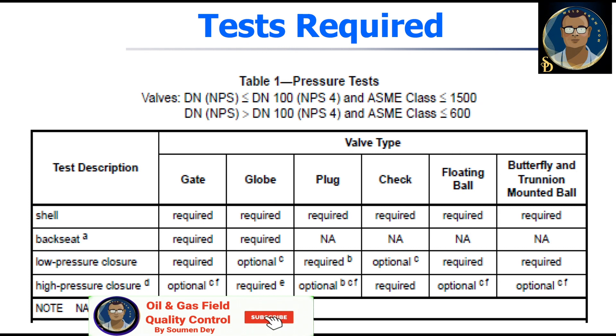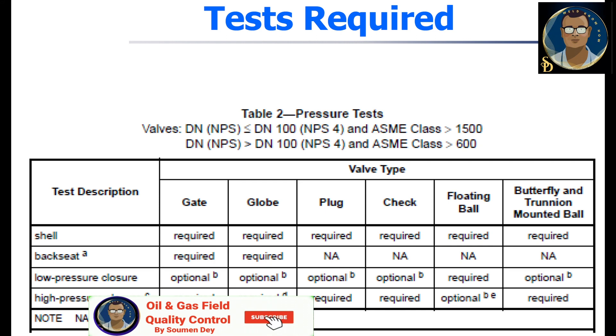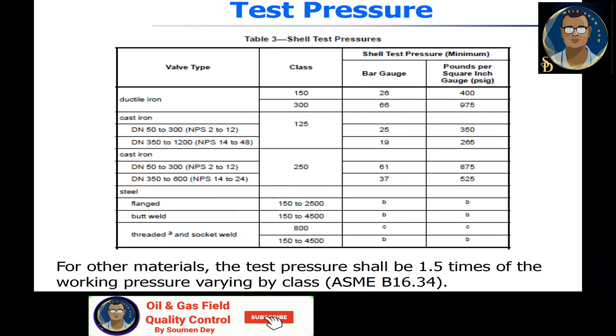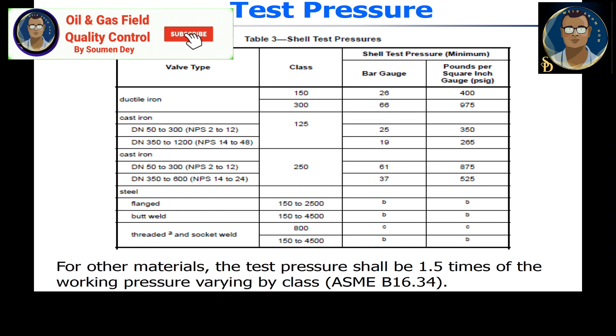Table 2 is a similar reference table — you can pause the video to take a snapshot. For the test pressure, Table 3 shows the shell or body test pressure. For example, NPS 2 to 12 inch at class 125, the shell test pressure minimum should be 25 bar, which is 350 psi. For other materials, the test pressure shall be 1.5 times the working pressure, varying by class per ASME B16.34.